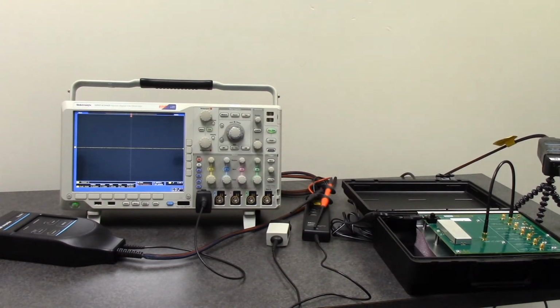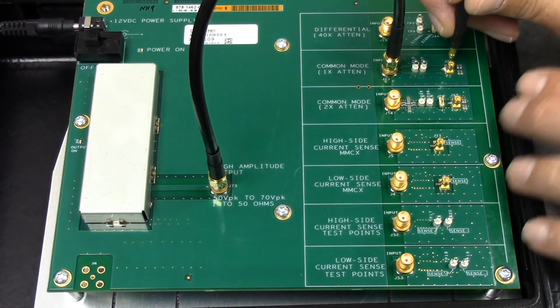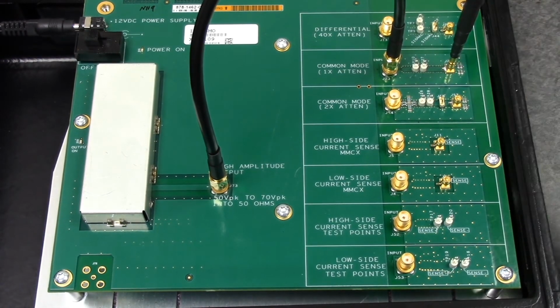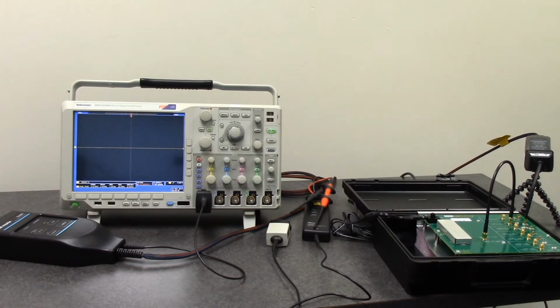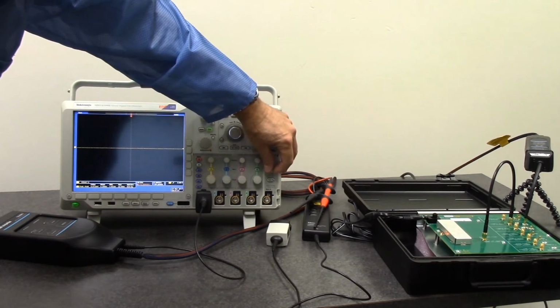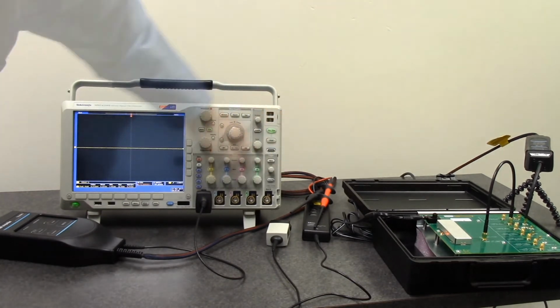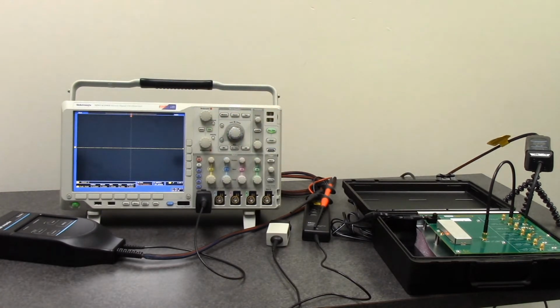Once that's complete, we can connect the IsoVu tip cable to the connector at J25 and turn the demo board back on. With IsoVu, the common mode signal is much smaller, so we will have to adjust the trigger level. So now you can see that we're no longer triggering. There's not enough common mode interference from the demo board to trigger the scope.